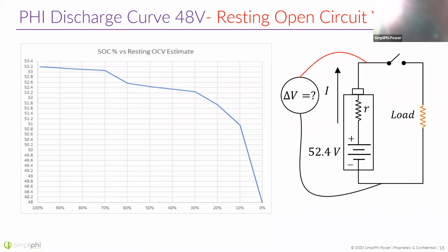This is the opposite when charging a battery. The voltage rises and rises, all the way up to 56 volts, even though the resting voltage at 100% state of charge is just over 53 volts. The amount of voltage drop below the resting voltage is proportional to current. So if I have a certain resistance and double the current, I'll double the amount of voltage drop below the resting voltage of the battery.